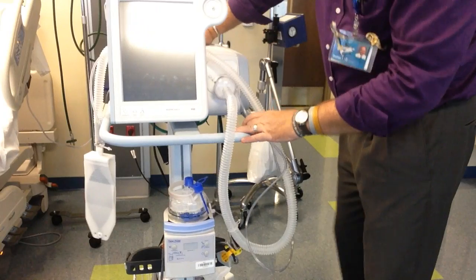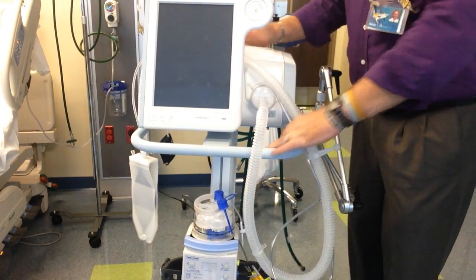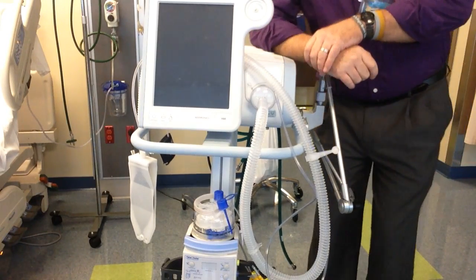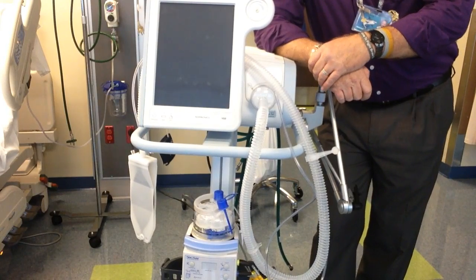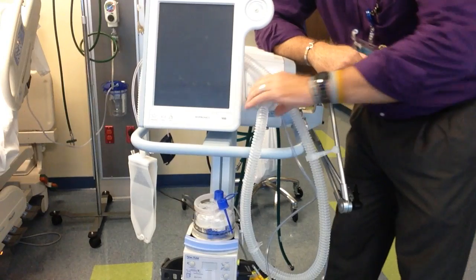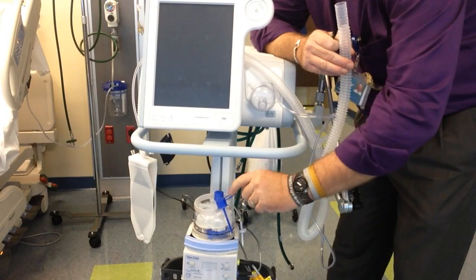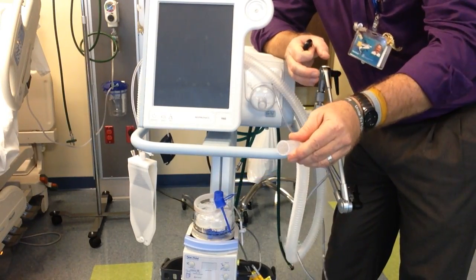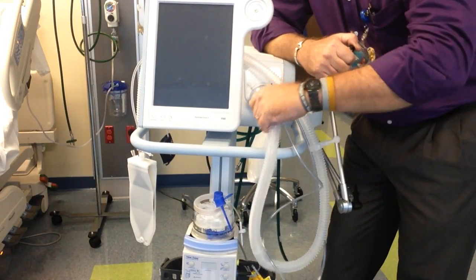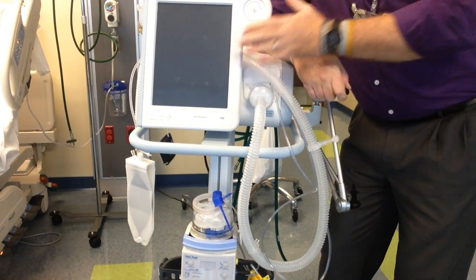That is the basics of the external portion of the Respironics V60 ventilator. Pressure limited, time cycled. You can use it with or without active humidification. If you're using active humidification, of course, you will have a hose coming from here to your chamber, from your chamber to here, or it'll go right there and you'll have another hose coming down, just like the high flow nasal cannula. In the next video, we'll go over some of the internal controls.